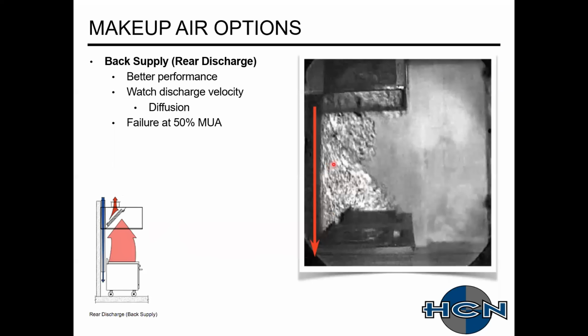Back return is actually one of the better performers in this test. Failure about 40 to 50%. The big thing with back returns when you're designing or working with them is, PF Chang's actually is one of the accounts I used to work on a lot. They pretty much had a standard design with back returns, and we typically would have a lot of problems with the woks getting blown out with their pilots because that air velocity was so high. So we had to keep it at a certain point. So we were basically designing 40, 50, maybe 60% makeup air, and then the remaining we were kind of dotting around the space with perforated diffusers or some other means to get that air into the space.